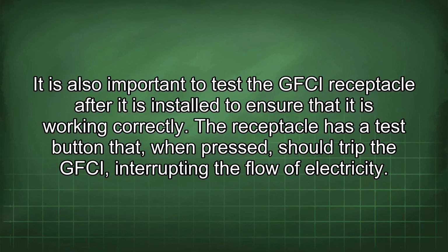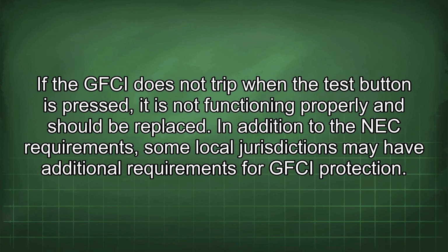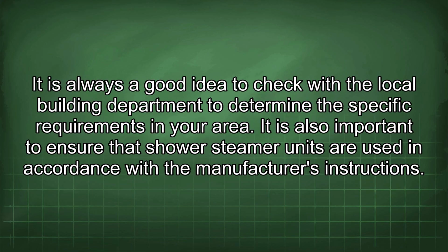It is also important to test the GFCI receptacle after it is installed to ensure that it is working correctly. The receptacle has a test button that, when pressed, should trip the GFCI, interrupting the flow of electricity. If the GFCI does not trip when the test button is pressed, it is not functioning properly and should be replaced. In addition to the NEC requirements, some local jurisdictions may have additional requirements for GFCI protection. It is always a good idea to check with the local building department to determine the specific requirements in your area.